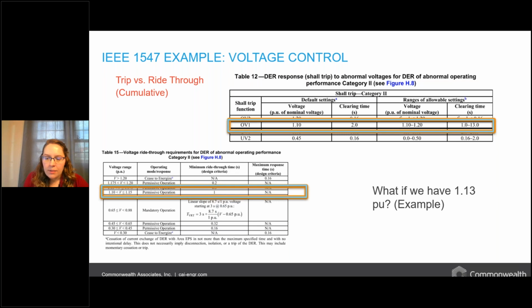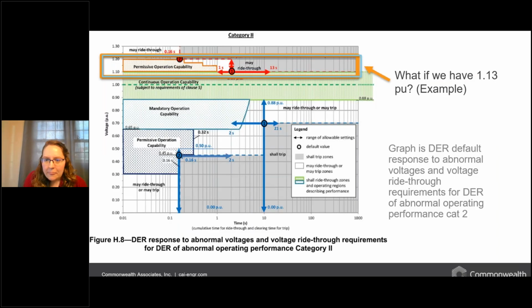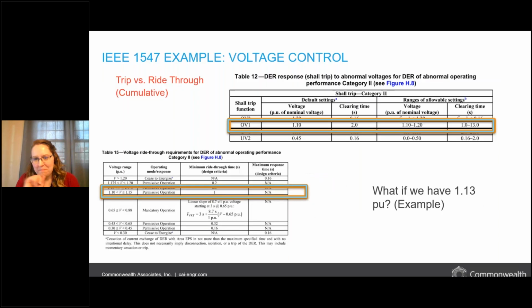So for our example, we talked about 1.13 per unit, or 113% of our anticipated voltage. So if we zoom in on our slides, as we've seen here, on the right, nope, we're good, one slide back. Yep, on the graph on the right, we see that 113 or 1.13 is considered an overvoltage condition.